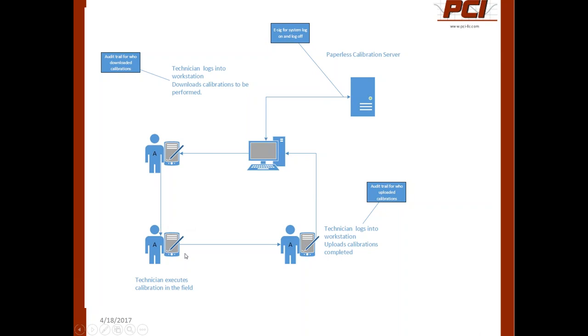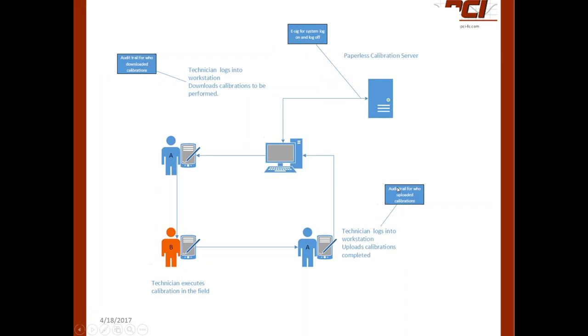They would take that handheld device out into the field, execute the calibration, come back, log into the workstation, and upload those calibrations. Those uploads would again have an audit trail showing the individual and when they logged everything back in. But what happens if it's a two-person calibration? This is where we ran into some data integrity challenges after deployment that we hadn't really anticipated.